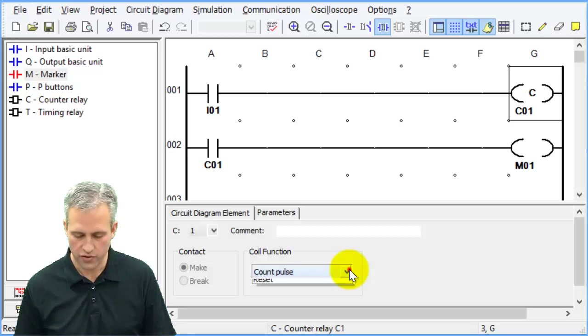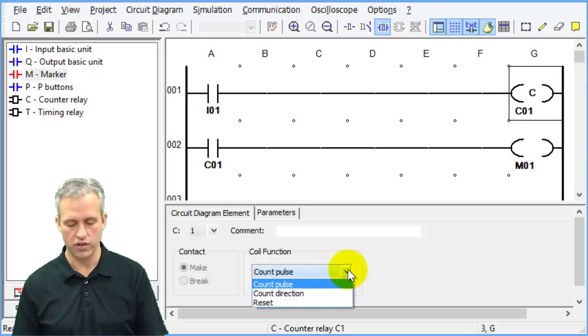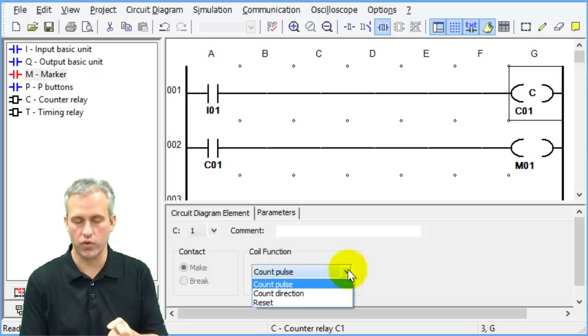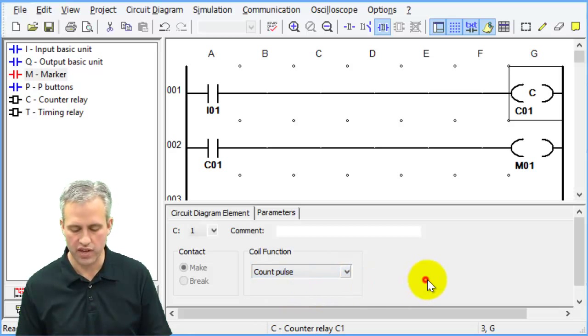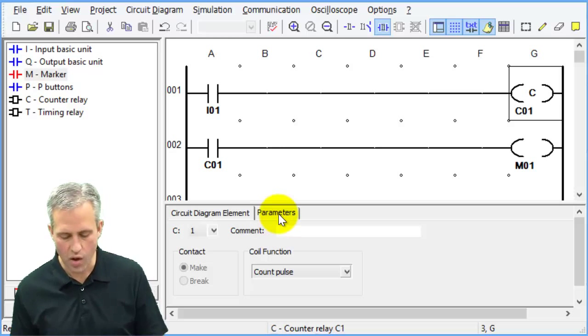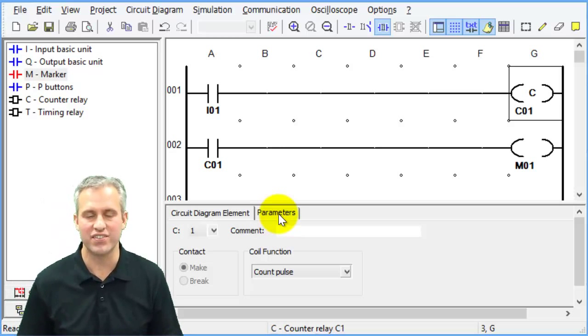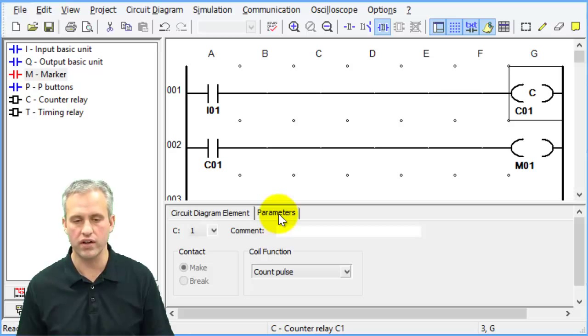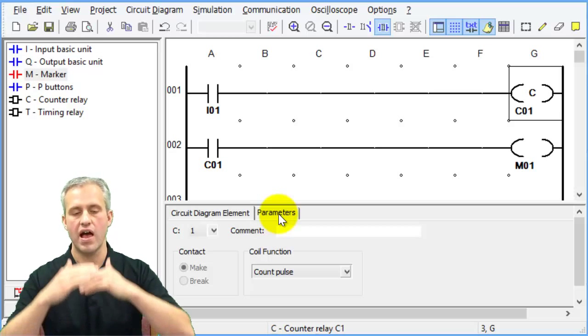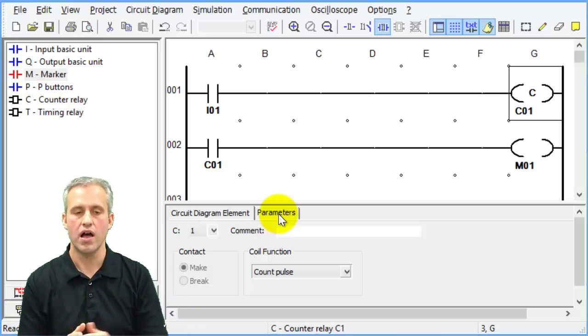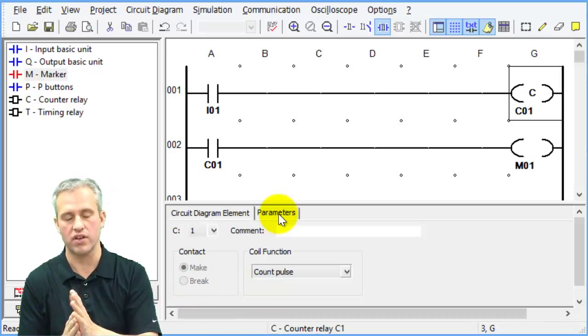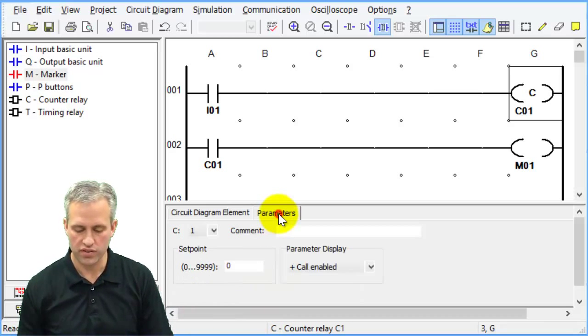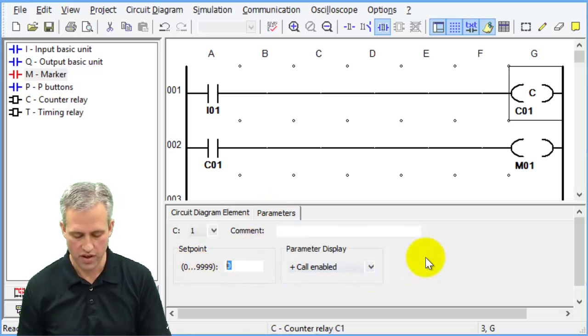Let's click on the counter and see what some of the options are. The first options are you can use a count pulse, a count direction, or a reset. The one that you care about most is count pulse. What I will say about a counter, a surprisingly common error, is a counter counts how many items have come through, and then when you hit a set point it does something different.